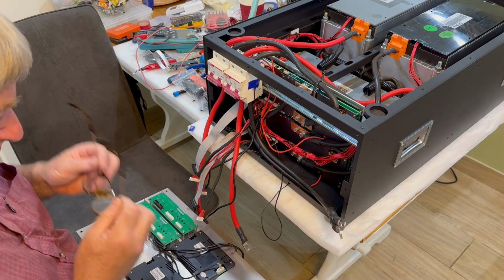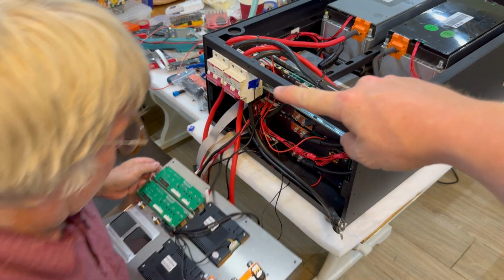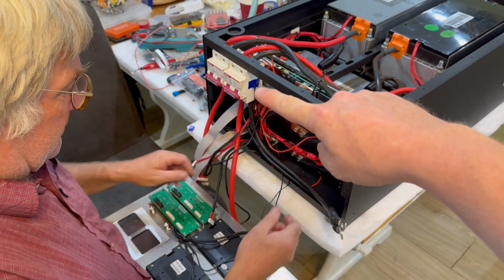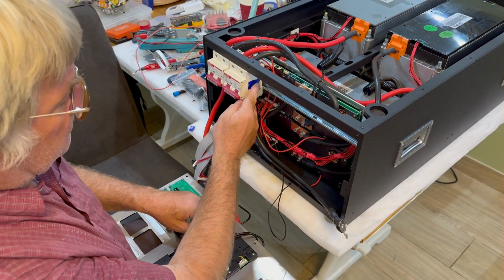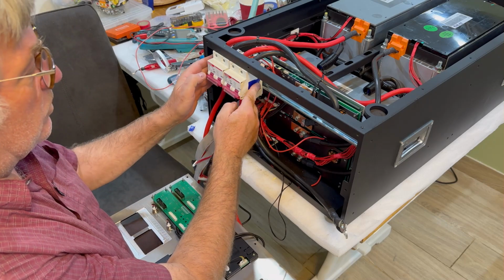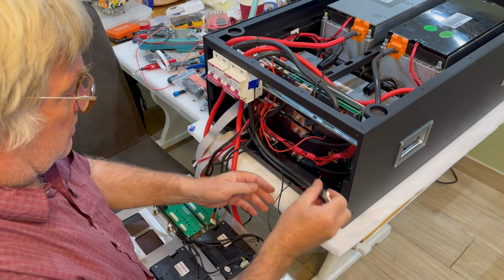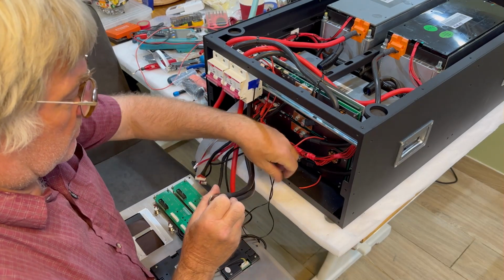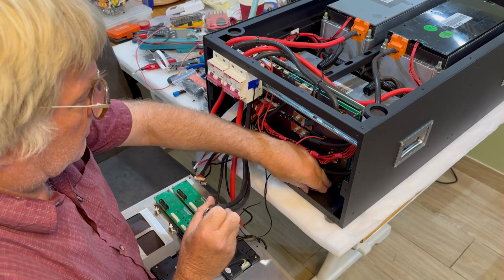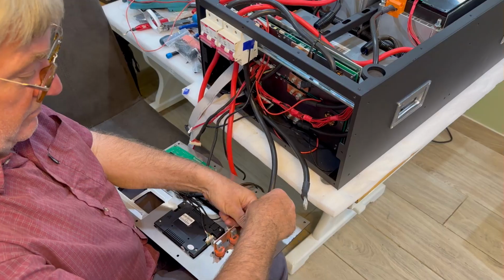You'll see that there's a small little temp sensor. We've got a spare one off the BMS, so we've actually attached that to the side of the breaker, just with a little bit of 2-pack resin glue on each side, just to hold that in place. Just gives us an extra reading off those.